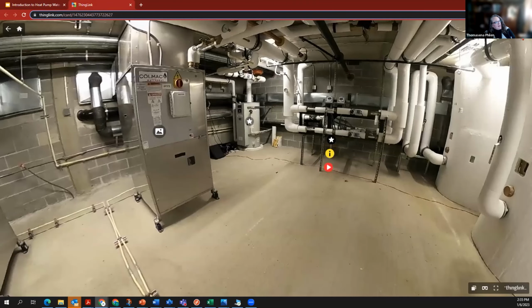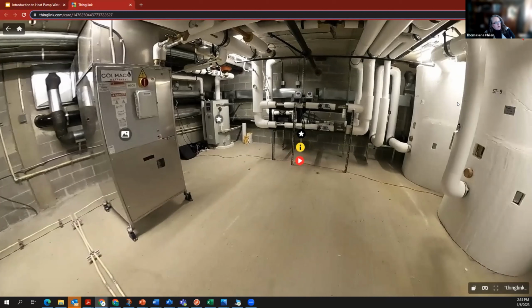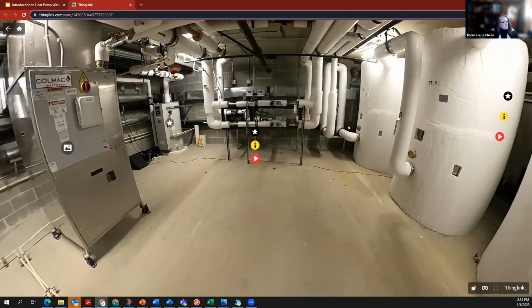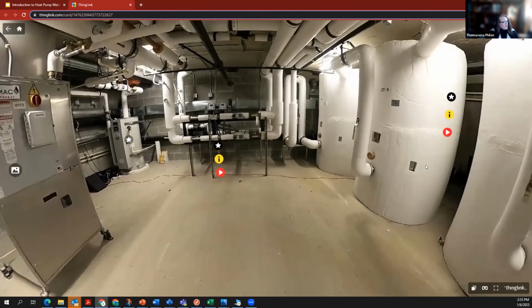These heat pumps maintain the temperature in these tanks at 140 degrees, which is too hot to come out of the tap. That means that you need to mix, as the technician, the design engineer, you need to mix cold water with the hot water at 140 degrees to where it comes out of the tap at a safe 120 or maybe a little bit less. And so these temperature mixing valves are here to do that job. If we were to take a look at the storage tanks, you will also notice that they are heavily insulated. And the reason for that is manyfold. And the first one is that you don't want the heat loss in the pipes or through the tanks. Even though they come insulated, additional insulation has been added.